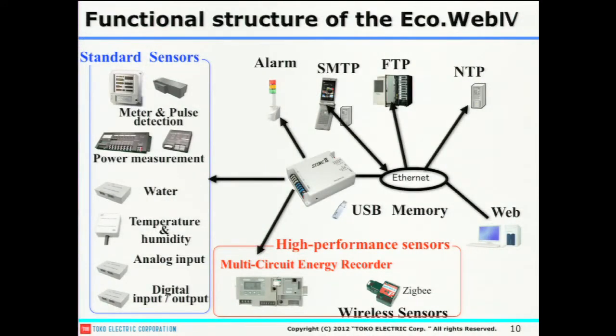So here's a little picture of how things would normally be attached: various sensors, electric-related sensors from meters. Usually when you have electric meters, these are pulsed signals, and it'll pick up the pulses and measure the signal. Japanese meters have different standards; U.S. meters have ANSI C12 tables and stuff, but Japanese meters are different, so this is geared towards Japanese meters here. If it's not a Japanese meter, we provide a Zigbee solution. There would need to be a radio attachment, but the Zigbee solution will allow you to read the ANSI 12 through the Zigbee Smart Energy profile. So it can work both in Japan and the U.S.